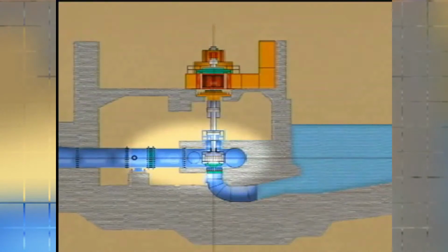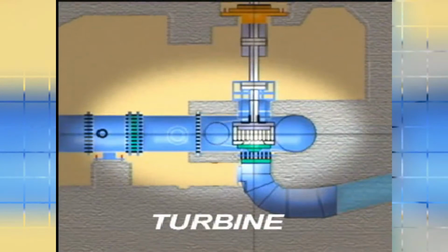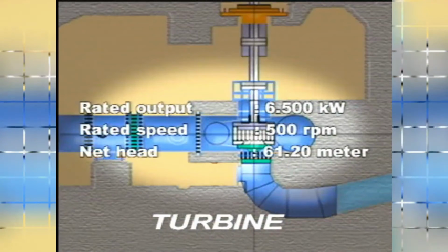Type and rating of the turbine: it is a vertical shaft, single runner, Francis type, and shall have an output of not less than 6,500 kilowatts at full guide vane opening, when operating at the rated speed of 500 revolutions per minute under a net head of 61.20 meters. Means provided to limit turbine output at heads above 61.20 meters to the rated output of 6,500 kilowatts. The best efficiency is desired when operating at 500 revolutions per minute under a net head of 61.20 meters.